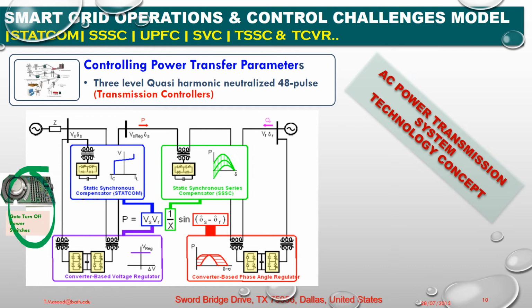Therefore, unless a converter is required to function in the two lagging current quadrants, only consuming reactive power while converting active power, converters applicable to flexible controllers would be of the self-commutating types. There are two basic categories of self-commutating converters. The first is the current source converter, in which the direct current always has one polarity, and the power reversal takes place through reversal of the DC voltage polarity. Second is the voltage source converter, in which the DC voltage always has one polarity and power reversal takes place through the reversal of the DC current polarity.